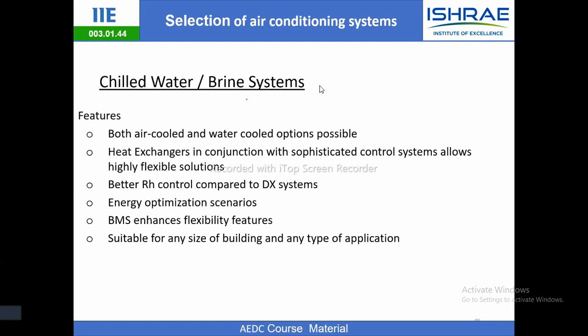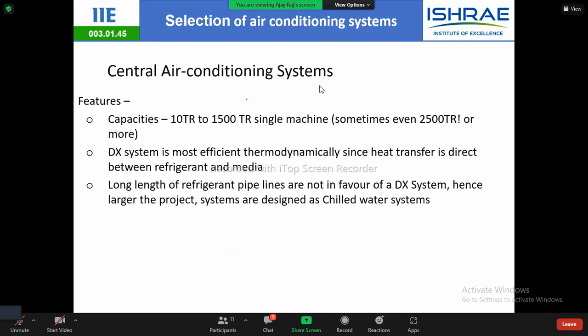Features: both air cooled and water cooled options are possible in case of a chilled water system, and it can be chilled water, it can be brine also. A heat exchanger in conjunction with a sophisticated control system allows high flexibility solutions, better RH control compared to a DX system. Energy optimization scenarios are possible. BMS enhances flexibility features, suitable for any size of building and type of application. Though here we are mentioning any size, practically what we have seen is that if your tonnage is more than 200 tons, that is each chiller, if let's say I am having two working and one standby and both the chillers are more than 100 TR, only then your chilled water system becomes economical.